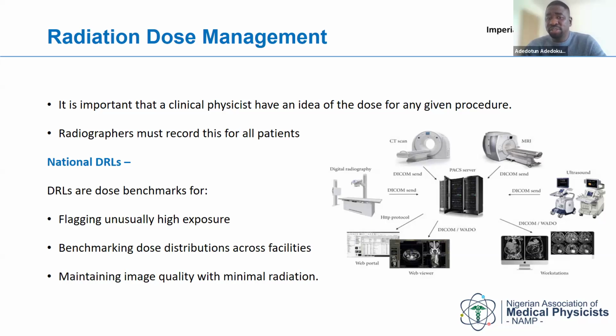These are just dose benchmarks for flagging unusually high exposures. Benchmarking dose distribution across facilities, you're able to compare from one facility to another. You have 3 Philips equipment. You can see for chest X-ray, one is giving a DAP of maybe 0.04 and the other one is giving 0.08. Why? That's like double. What's the difference? You need to know why.